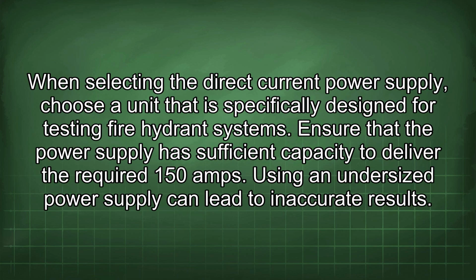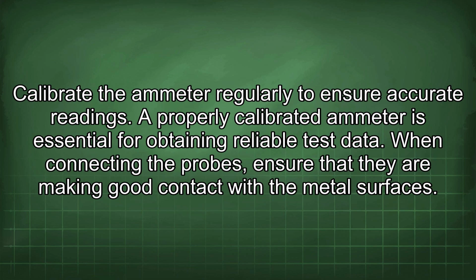When selecting the direct current power supply, choose a unit that is specifically designed for testing fire hydrant systems. Ensure that the power supply has sufficient capacity to deliver the required 150 amps. Using an undersized power supply can lead to inaccurate results. Calibrate the ammeter regularly to ensure accurate readings. A properly calibrated ammeter is essential for obtaining reliable test data.